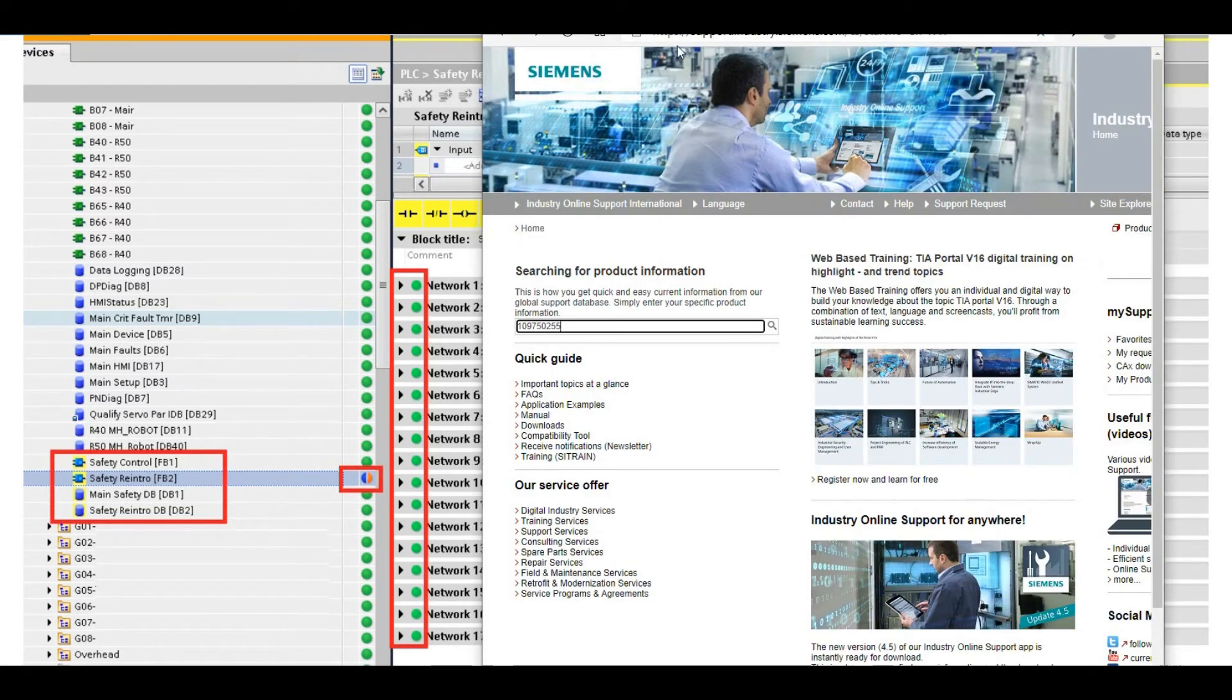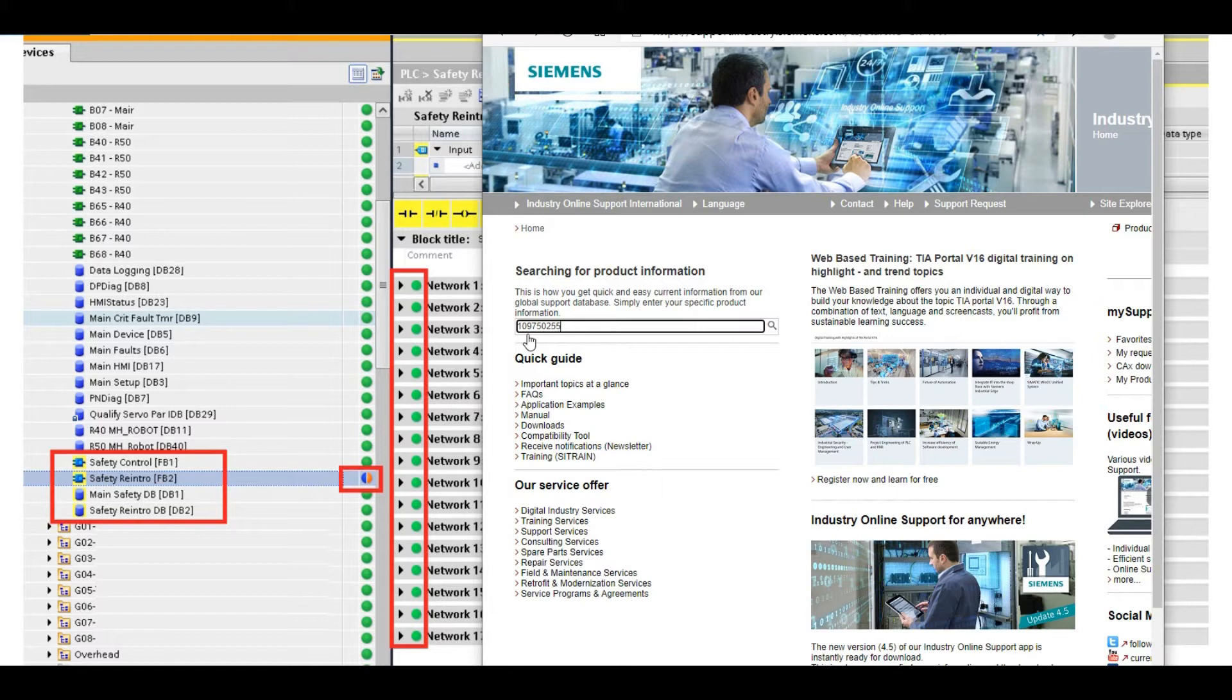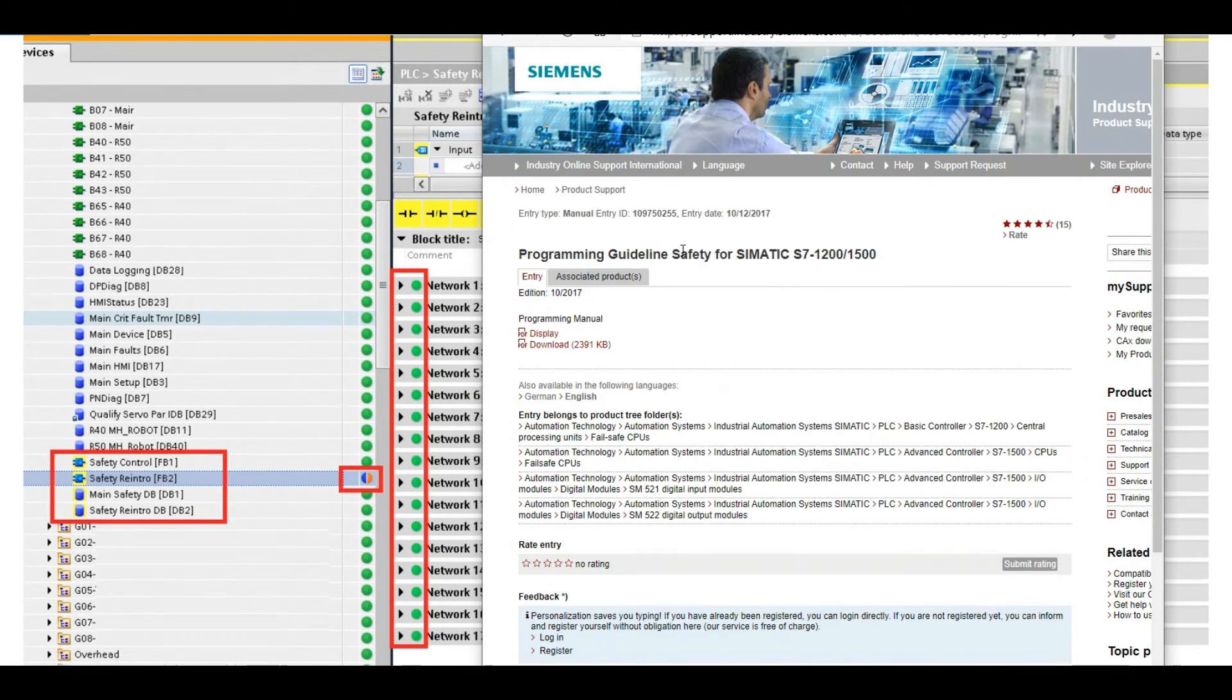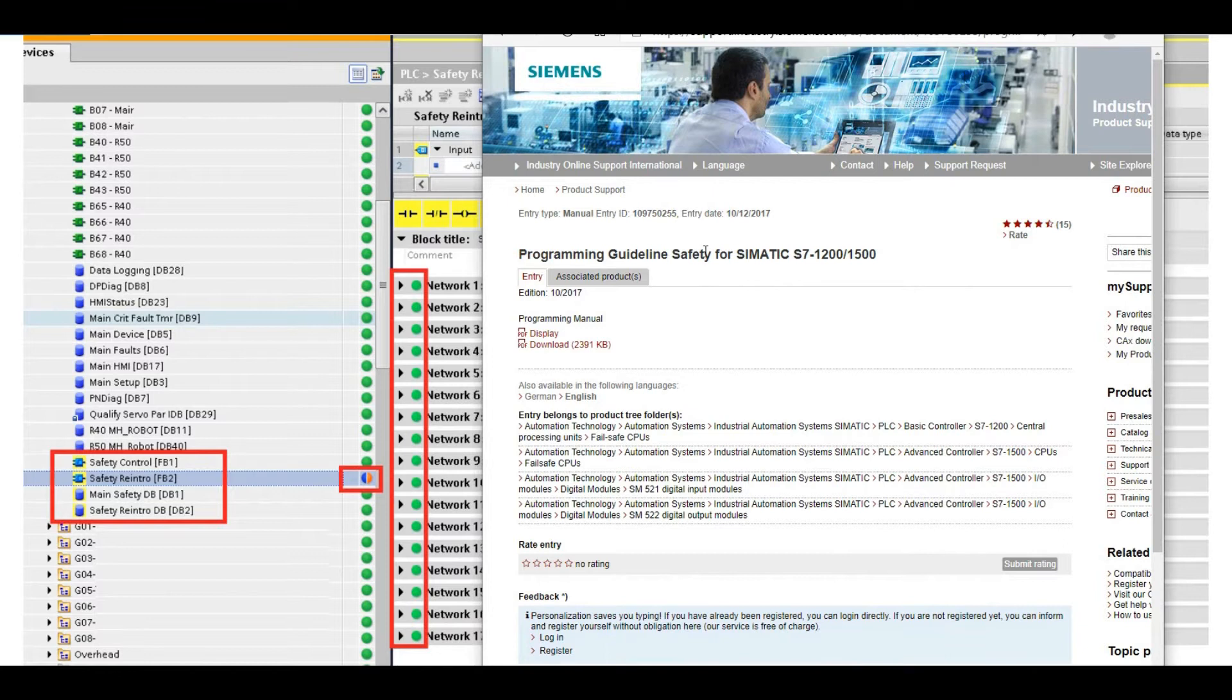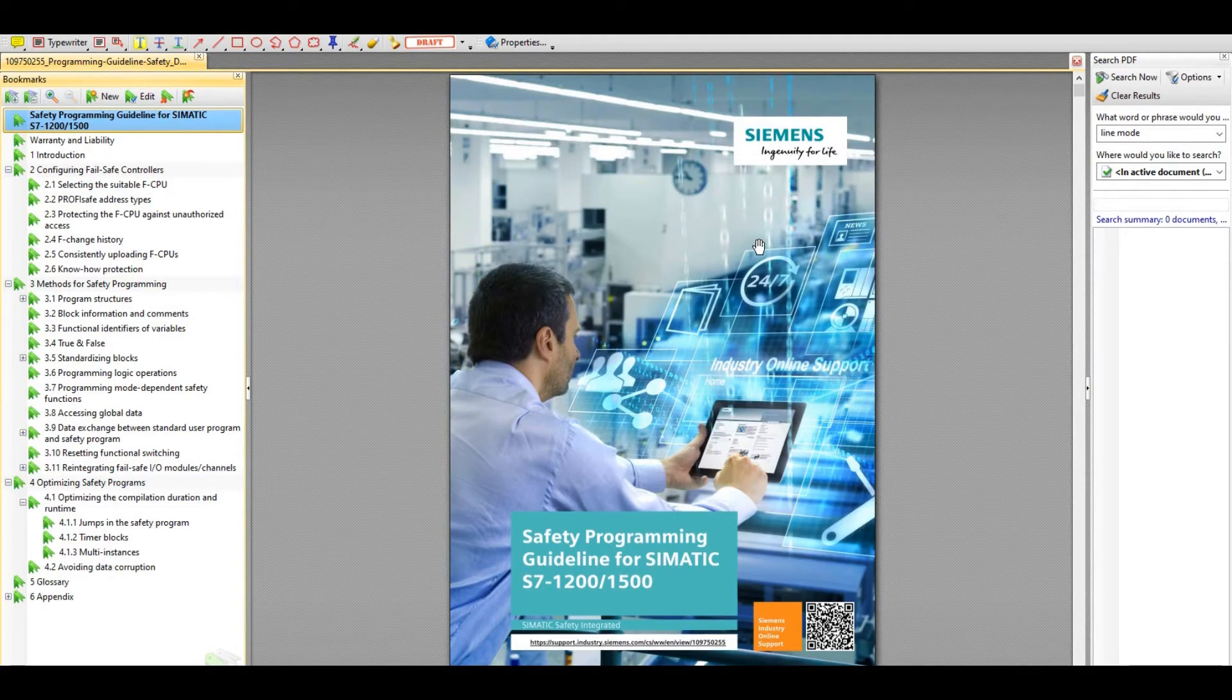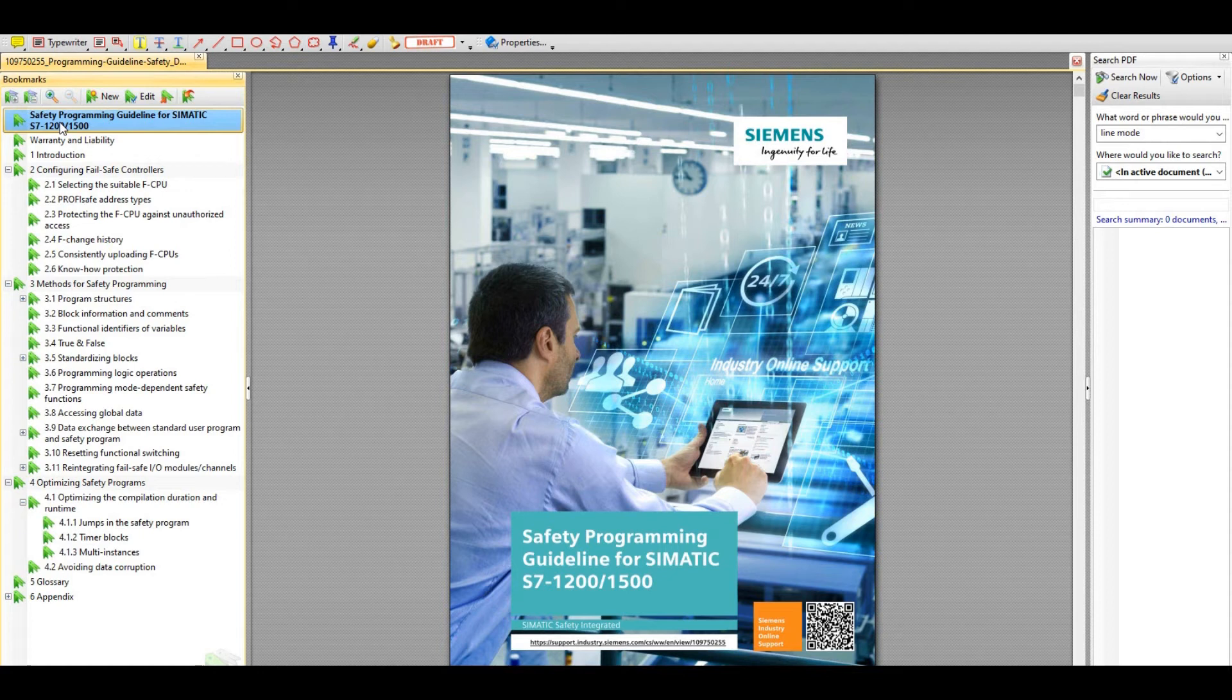If we go to the Siemens support website, support.industry.siemens.com and search this ID number 109750255, we will find one document: Programming Guideline Safety for Siemens S7-1200 and 1500. That also works for S7-300 safety. You can download this PDF file. This is a very good document that talks about the programming guideline, how to program the Siemens S7-1200 and 1500 safety logic.